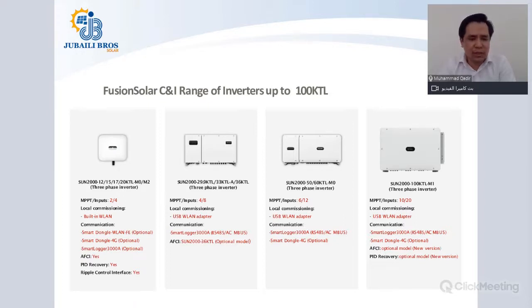Number 3rd option is the SmartLogger 3000A. So these are all optional devices, not must. If you need the remote monitoring, that is the device that you must use. AFCI, the new inverter and the old inverter both have this feature. The PID recovery will be the feature with M2 version. Ripple control interface is also feature with both the M0 and M2 version.